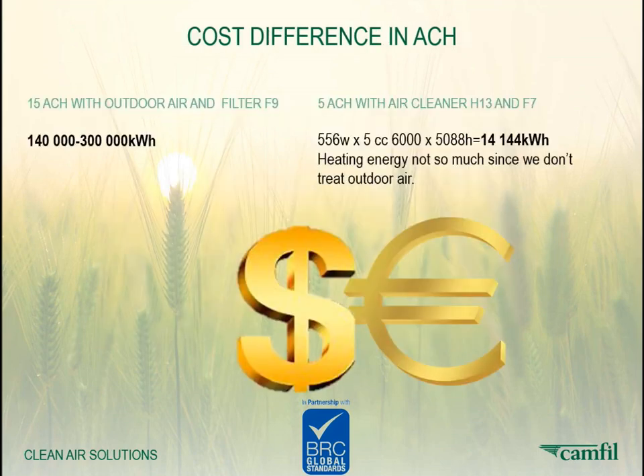If the source of pollutants is inside a building, it's most of the time more energy efficient to recirculate it locally. A lot of countries have minus degrees during winter time or hot during summertime. In this example, we could have 10 to 20 times higher energy consumption during, for example, a cold period of 6 months. This is, of course, depending on the circumstances and the temperature and efficiency of the heat exchanger and the number of air changes.